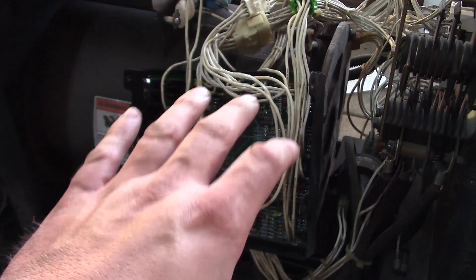Anyway, I called him back because I didn't know what that meant, so he had me disconnect the other two wires from the rectifier to rule out the rectifier being shorted. I did that, and the 110 volt was still good. So that brings us down to this control board being bad, the excitation control board. This is only used for the welding output - the excitation field, I guess, is self-regulating.